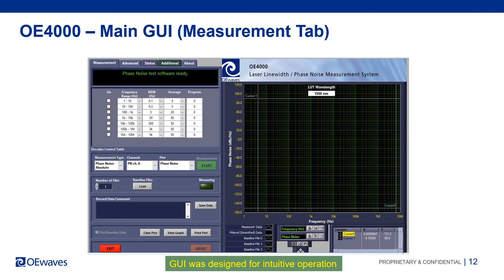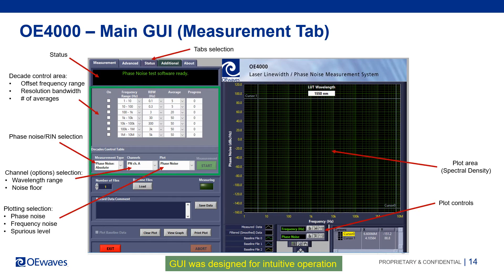Next, we will share some slides showing the system GUI and its features. The GUI was designed with the user in mind — it is intuitive and easy to use. The main GUI has tabs on the left side and the plot area on the right. The parameters the user can select before starting a measurement include the frequency offset range, resolution bandwidth, number of averages, phase noise or RIN selection, and channel or band selection.